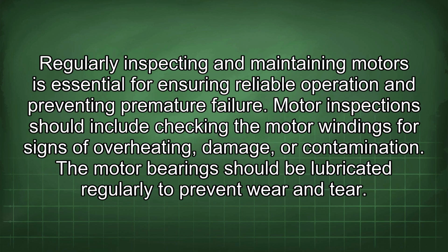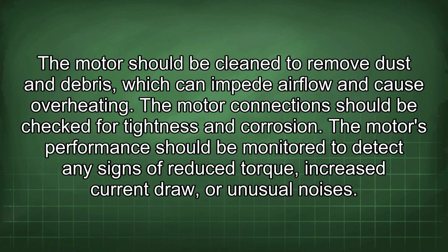Regularly inspecting and maintaining motors is essential for ensuring reliable operation and preventing premature failure. Motor inspection should include checking the motor windings for signs of overheating, damage, or contamination. The motor bearings should be lubricated regularly to prevent wear and tear. The motor should be cleaned to remove dust and debris, which can impede airflow and cause overheating.